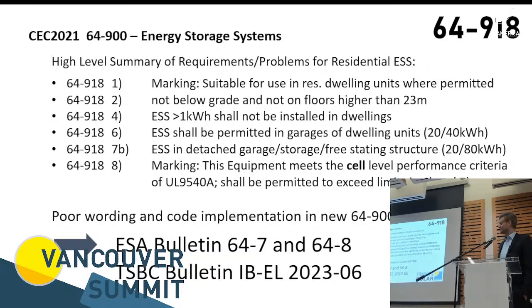The good news is that there are 2 bulletins available. The ESA in Ontario brought out 2 bulletins, 64-7 and 64-8, that clarify what you actually can do, even though the code says that you cannot do it. And then, luckily for BC, there's also an installation bulletin, the 2306, that came out that also has certain requirements for the installation of battery storage systems in residential dwellings.